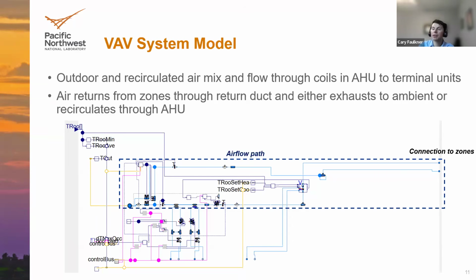And then there's also the connection to the zones to have the air return from the VAV or from the zones back into the air handling system through the return ducts, where it's either exhausted to the ambient or recirculated back through the air handling unit. And then there's also this section here, which describes some of the controls and includes the logic needed to control things like the fan and the coil valves, which I'll talk a little bit more about later. And then there's the connection to the water sources as well to provide the heating and cooling.